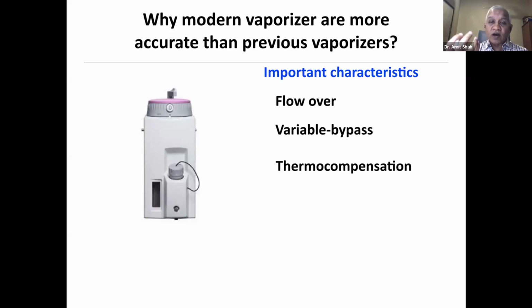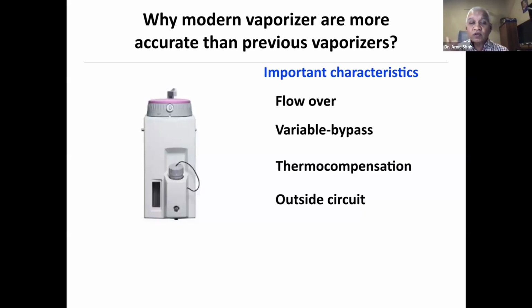Now, every time inhalation anesthetic is taken over, new inhalation anesthetic will form. As we know, it needs kinetic energy to come out, so it loses kinetic energy, which is always in the form of heat. So the temperature of the liquid will go down, and we need to have a mechanism by which it compensates for the temperature drop. They are not in our main circuit like the Bain circuit. It is inside the anesthesia machine, so outside the circuit. I'll show you the importance of that. And they are agent specific. So these are a few important characteristics of the modern vaporizer.